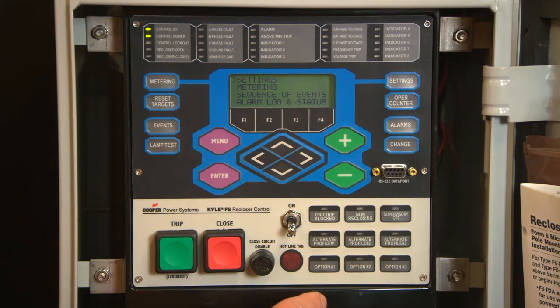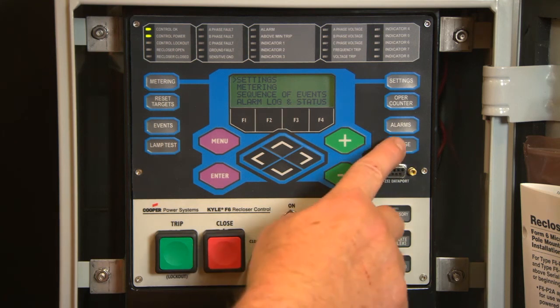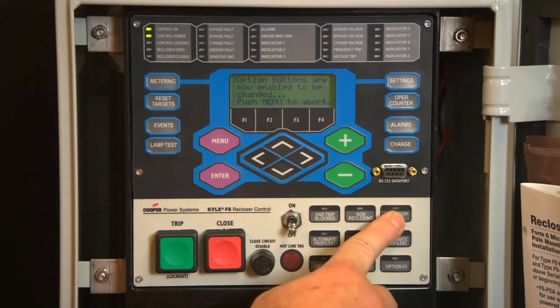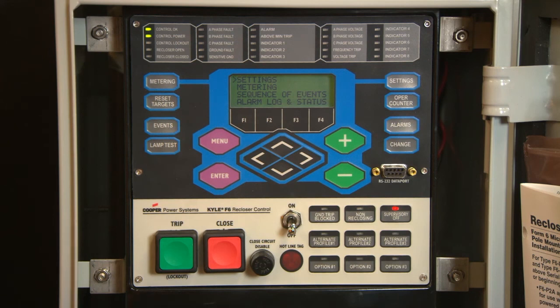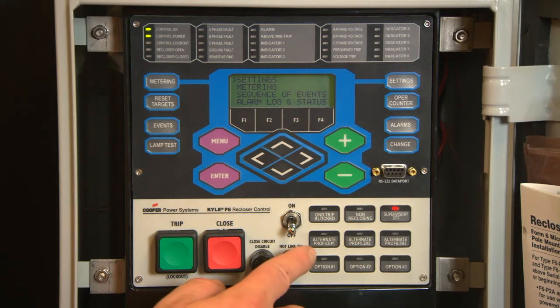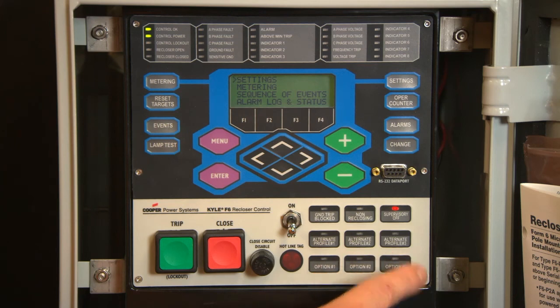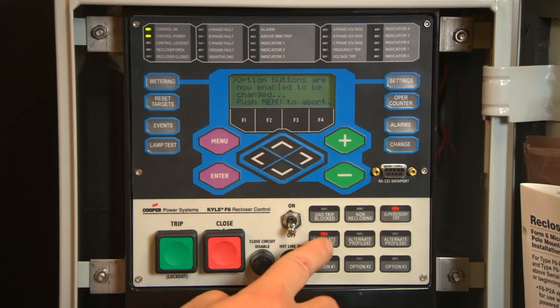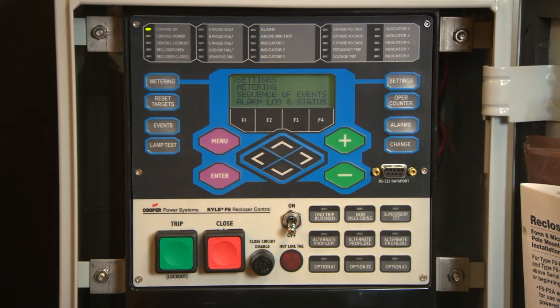If this unit is connected to OGCC communications, supervisory functioning would be provided. If supervisory is not connected, press the Change button followed by Supervisory Off. These reclosers are normally not connected to the OGCC. There are 3 sets of alternate programs. If these were programmed, they could be activated by pressing the Change button and then selecting the active profile. There would be new settings in the control. To return to the normal control settings, press the Change button. This will remove the alternate settings.